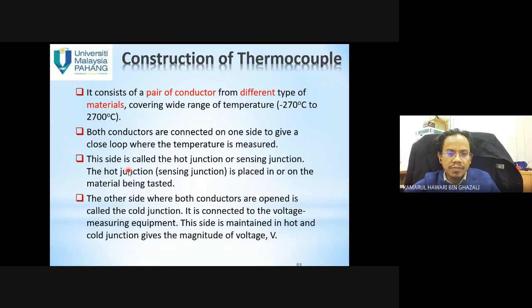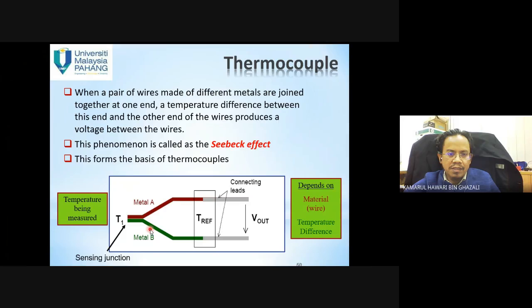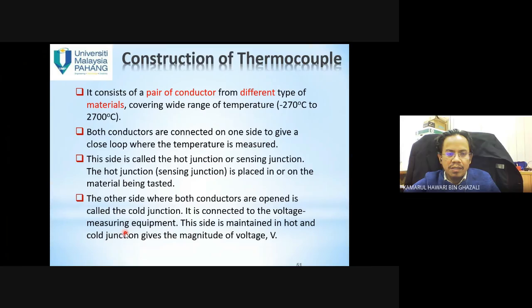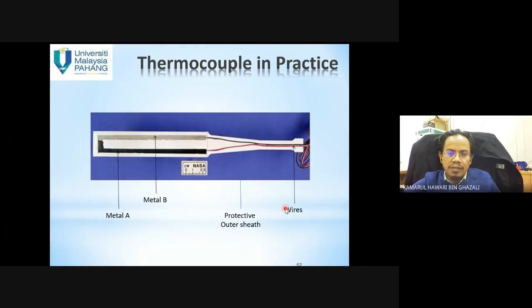So the sensing junction is touched to the material being tested. The other side, where both conductors are open, is called the cold junction. It is connected to the voltage measuring equipment. So this side is maintained, and the hot and cold junctions give the magnitude of the voltage. So that is the construction of the thermocouple. This is the physical outlook of the thermocouple.